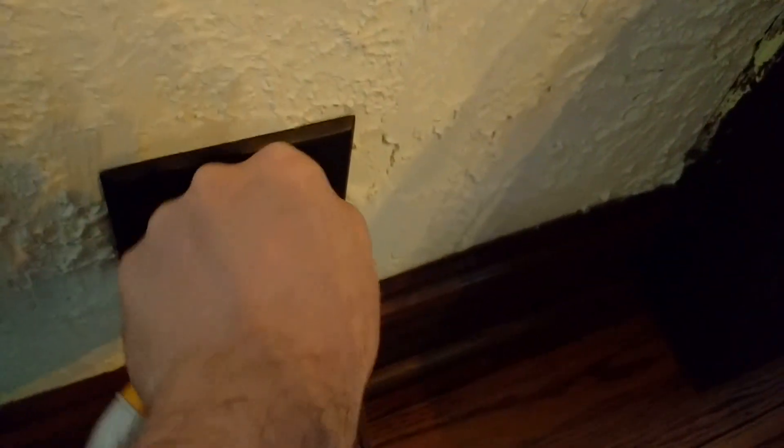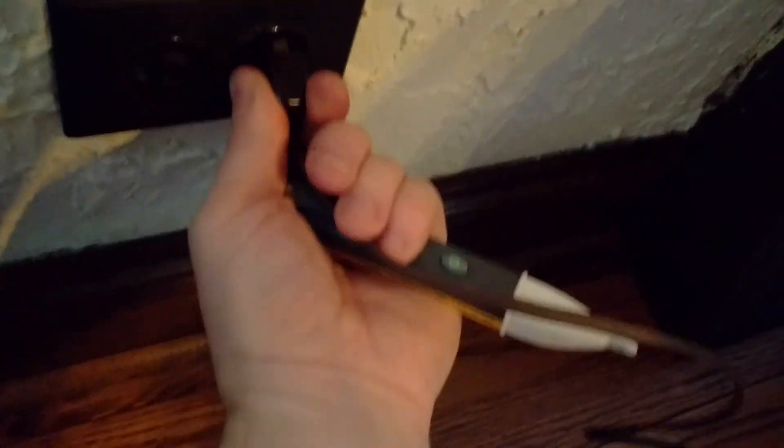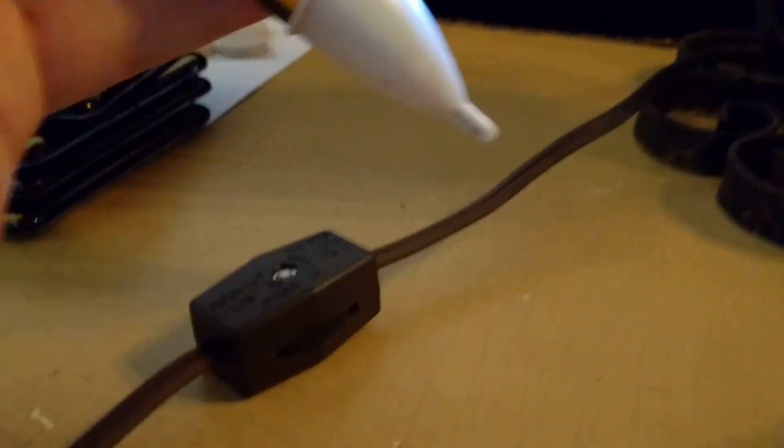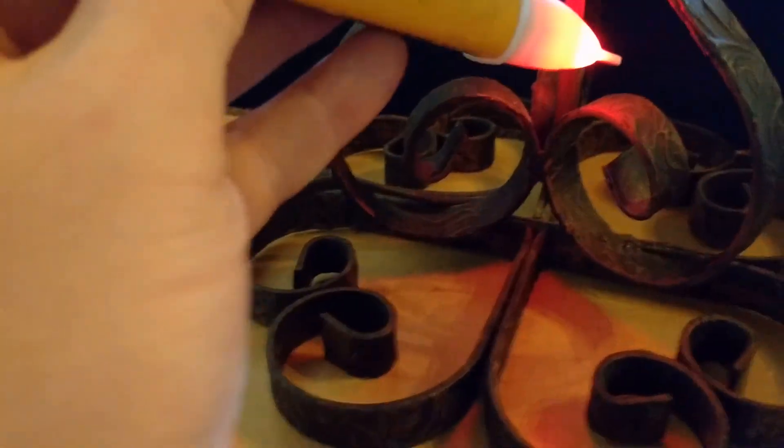So now we take the plug, we plug it in the wrong way. Now, here's the power again. Guess what? The light's still off. See how it's still hot? Check this out. See? There's power down there in that light bulb, even though the switch is off.